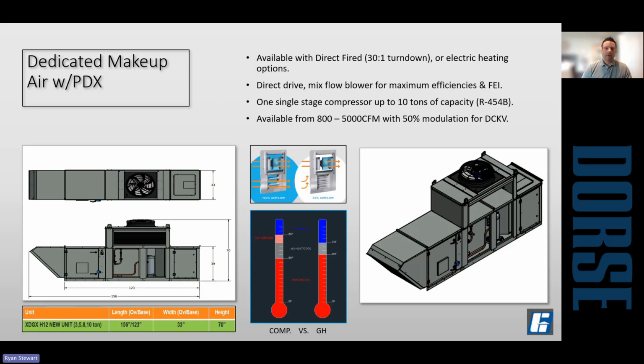This unit here is unique to Greenheck. As far as I've seen, they're still the only manufacturer offering a direct fired makeup air that has packaged DX cooling with the R454B refrigerant. This one right now is single stage, limited to 10-ton capacity. It's available from 800 to 5,000 CFM, and it's capable of the full 50% modulation range.